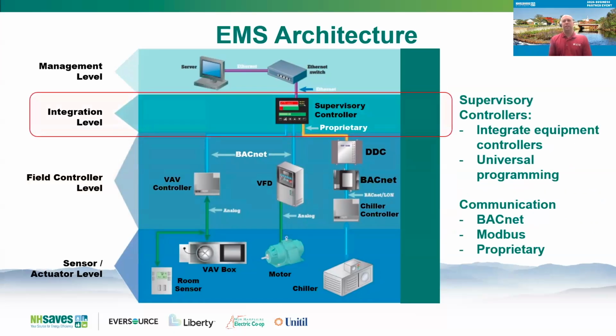Now, at the integration level is where all of those equipment controllers get integrated to a common platform. And now you can have programming, universal programming, such as schedules for the overall building that get driven down from the integration level. And again, if the network from the equipment controller to the supervisory controller is severed, then it would default back to whatever's on the equipment controller itself. But think of the supervisory controller as the main brain that sits on top of all the equipment controllers and maintains a common platform. At this level, communication is really important.